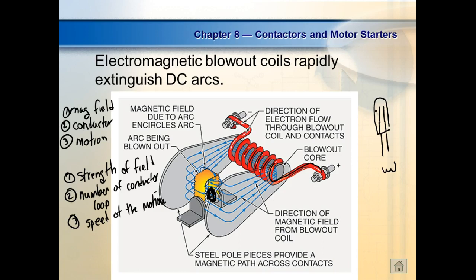What we have problems with is taking a circuit under load and doing what? Breaking it. So what happens when it breaks? This magnetic field comes collapsing back into this coil right here, right? And what happens now? It depends on the number of turns and the speed of the motion. Contacts open real fast. And what that does is this is going to reverse the magnetic field and cause the magnetic field to flow between these plates, and the actual magnetic field blows the arc out. So you'll see these on big DC. We don't have them on AC.